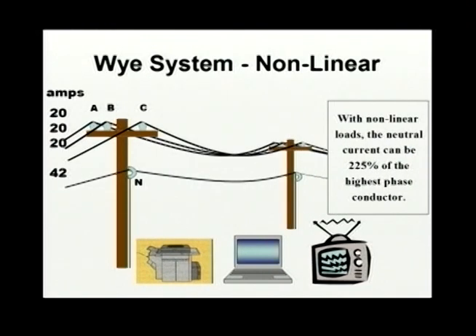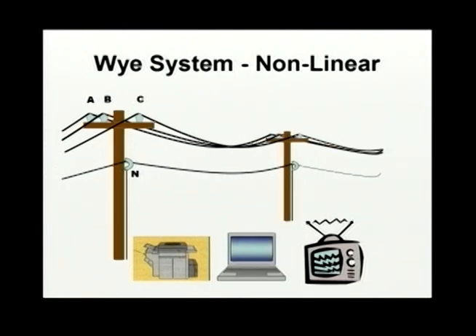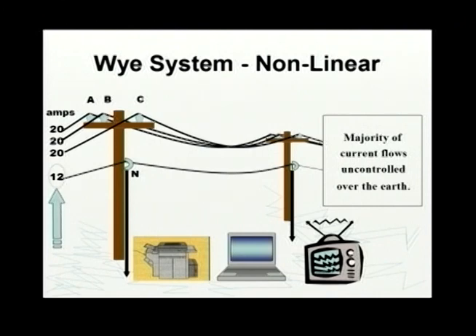With nonlinear loads, such as the computer, TV, and so on, the neutral current can be 225% of the highest phase conductor. Notice that A, B, and C, the phase conductors, are carrying 20 amps each. The neutral, which is supposed to return the current to the substation, is 42 amps, or 225% of the highest phase conductor. With nonlinear loads, the majority of the neutral current flows uncontrolled over the earth and in the air. Now we have the earth and all the surrounding environment contaminated with dirty electric current.